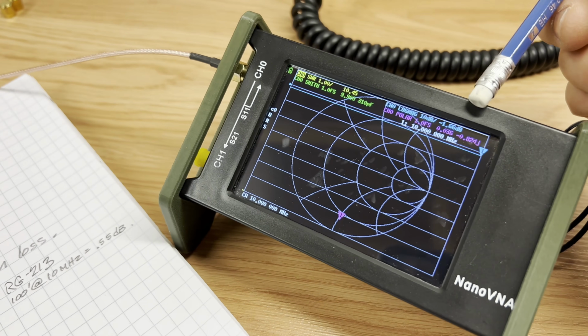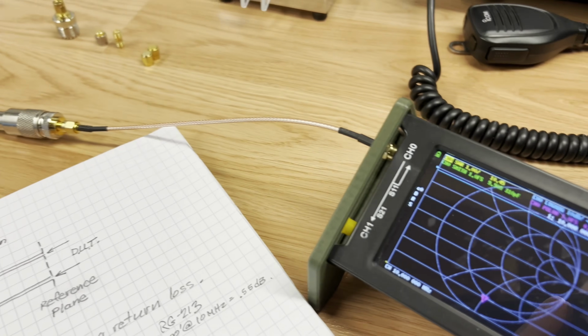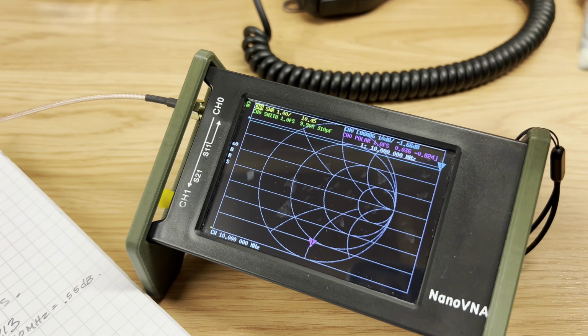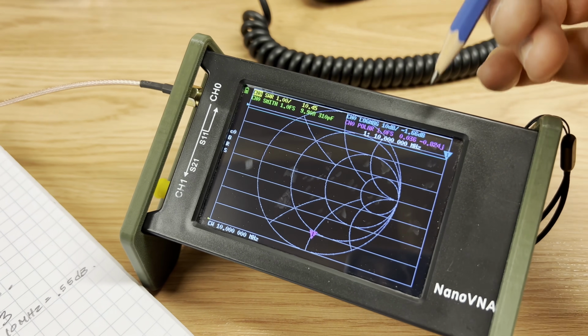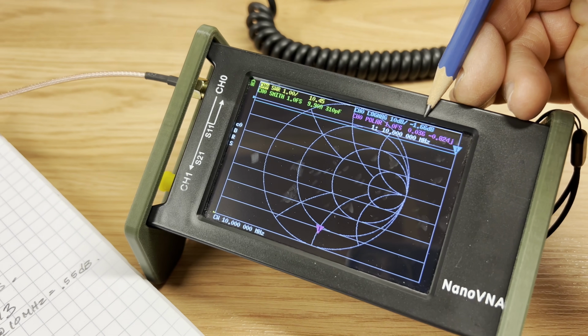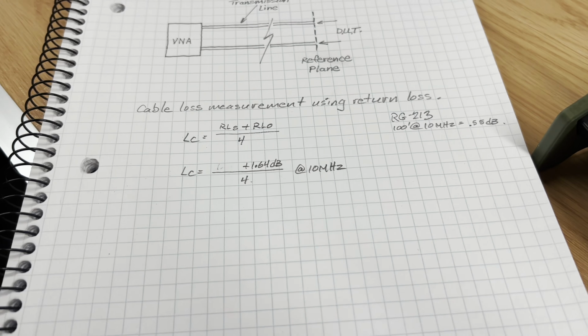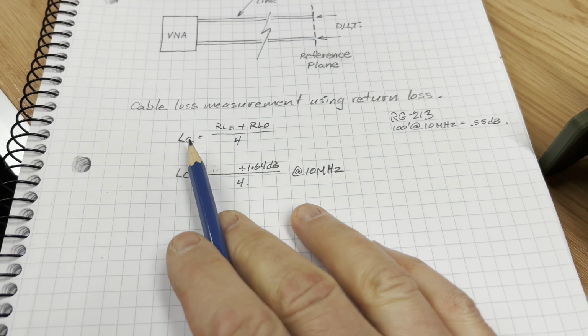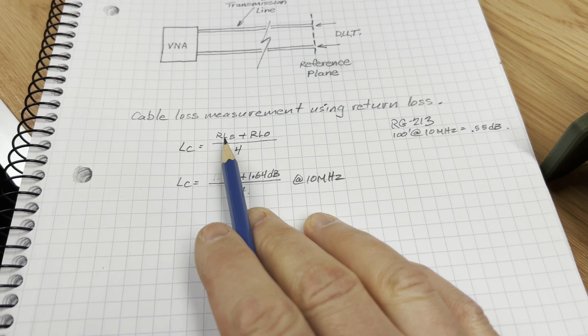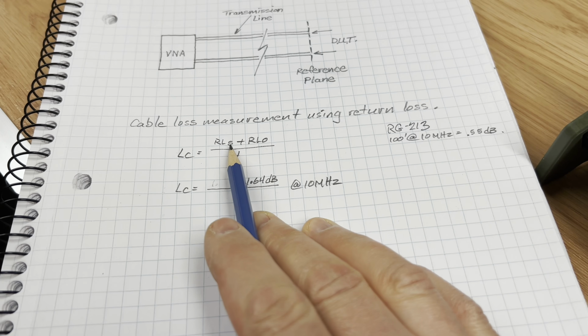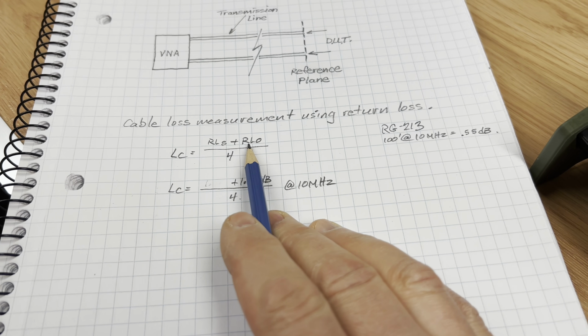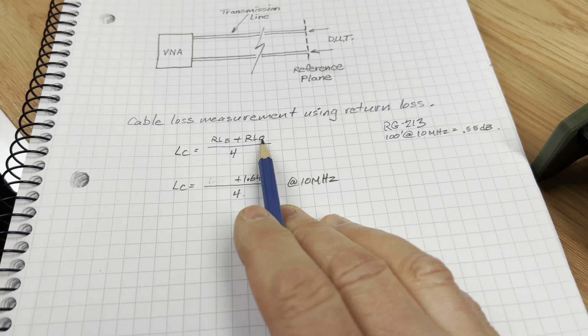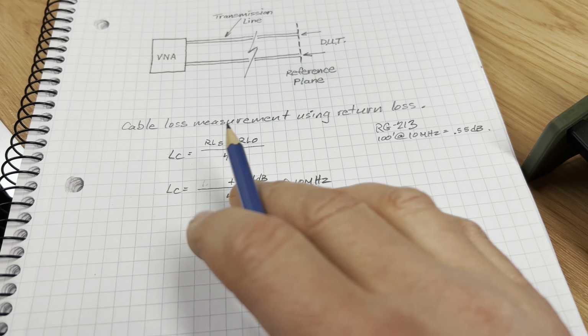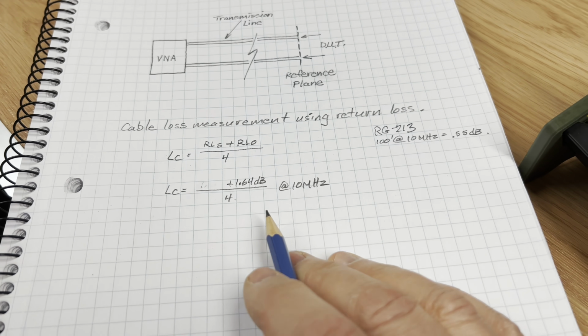So we've hooked up here and got our first reading at 10 megahertz, and you can see negative 1.66 dB. We did this in a previous video: the total loss of the cable equals the return loss with the cable shorted plus the return loss of the cable open, divided by 4. So this is the formula for calculating that.